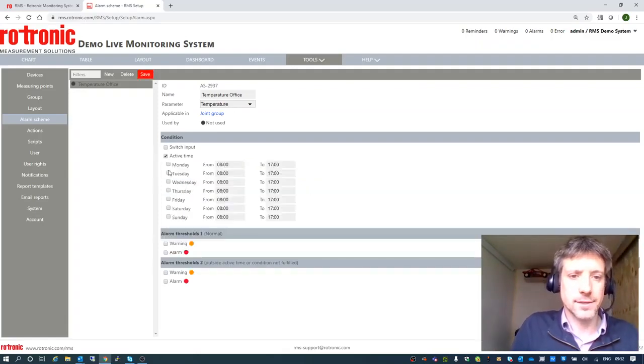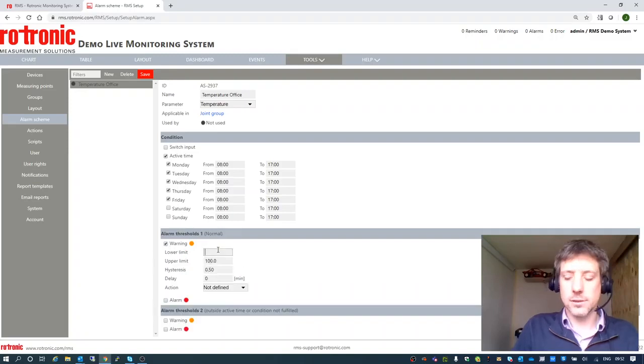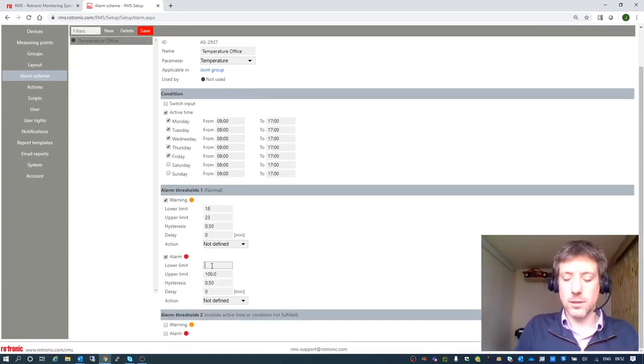Okay, I'm going to choose an active time. I only really care about alarms while I'm using this space. I'll leave this at 8 to 5. And I want warnings from, say, 18 to 23 with no delay. And I'm going to have an alarm message at 15 to, say, 25. And I might put a 15-minute delay on that one.